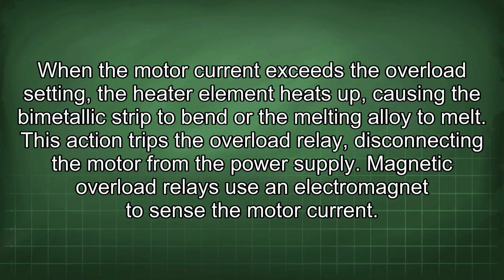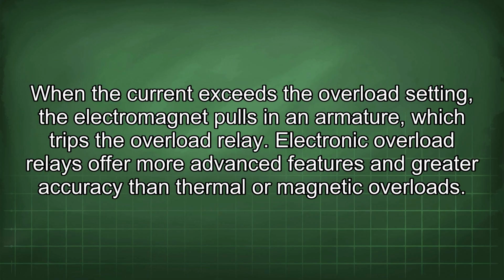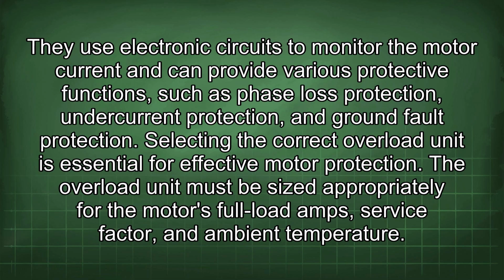Magnetic overload relays use an electromagnet to sense the motor current. When the current exceeds the overload setting, the electromagnet pulls in an armature, which trips the overload relay. Electronic overload relays offer more advanced features and greater accuracy than thermal or magnetic overloads. They use electronic circuits to monitor the motor current and can provide various protective functions such as phase loss protection, undercurrent protection, and ground fault protection.